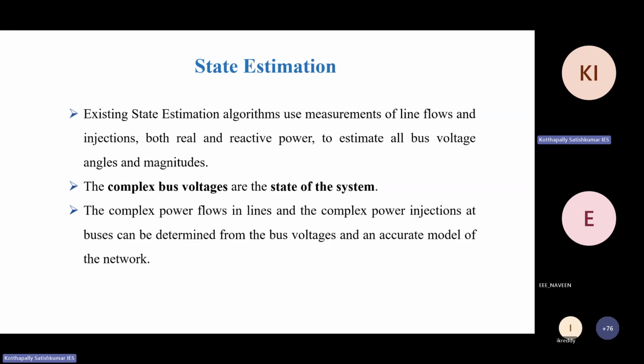So if you know the complex bus voltage of each substation, you can know the state of the system, whether it is really in emergency mode, like if the phase angles are in the range of 30-40. Using these phase voltages, you can calculate and tell the system state. That's why state estimation says, as my teacher used to say, if you know the bus voltages, you can tell everything about the system.